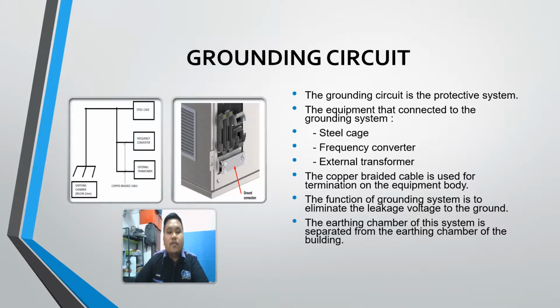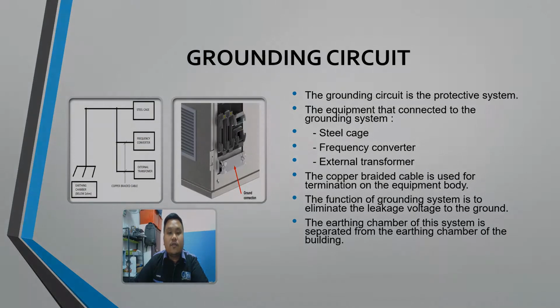For the high voltage grounding system, the value of the resistance must be below 2 ohm. But for the building grounding system, it must be lower than 10 ohm. The grounding system is to protect the equipment from leakage current or voltage and to protect the student from electrical shock due to the body of the equipment being highly conductive.